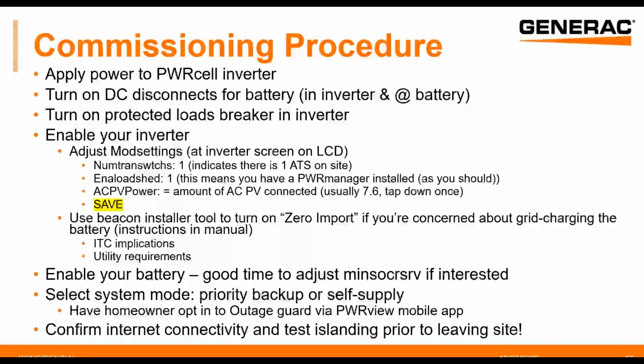Basically, it's going to take your AC voltage and rectify it, turning it into 380 volts DC. And then you're going to go to the inverter mod settings and adjust number of transfer switches to 1, which indicates that you have 1 transfer switch on site, which will be true if you're AC coupling. And then you'll change ENA load shed, which stands for enable load shedding, from 0 to 1. This is telling the inverter that you have a power manager and we should do our load shedding sequences in a grid outage.